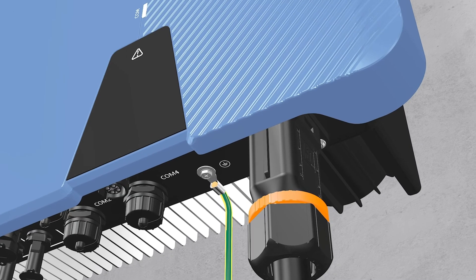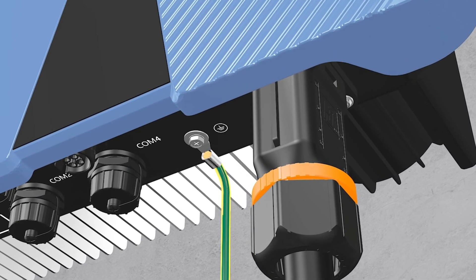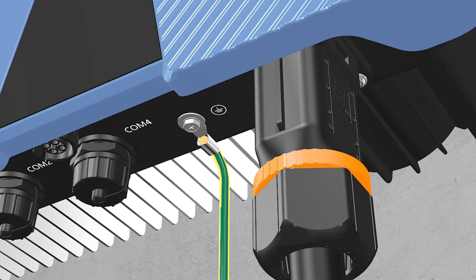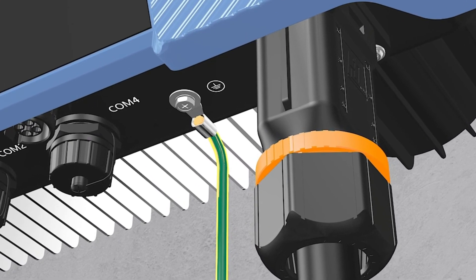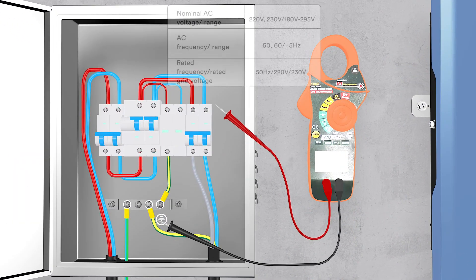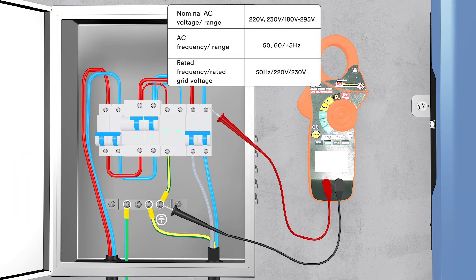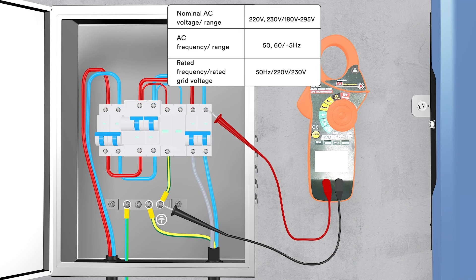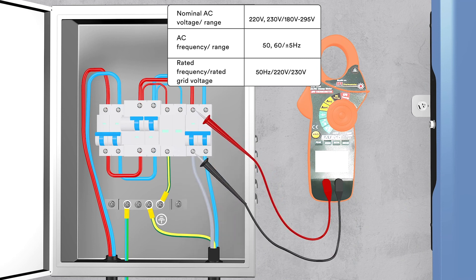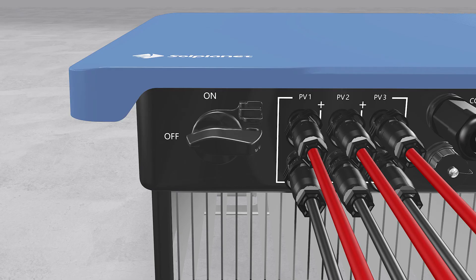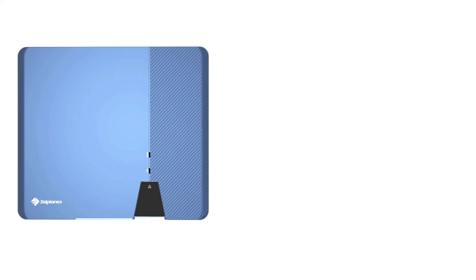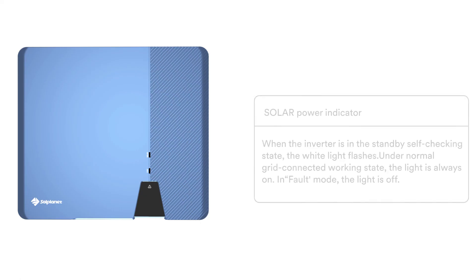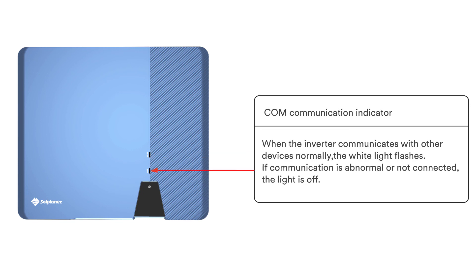Check the PE connection with a multimeter. Make sure that the inverter's exposed metal surface has a ground connection. Check the grid voltage. Check that the grid voltage at the point of connection of the inverter complies with the permitted value. Switch on the miniature circuit breaker and DC switch. The inverter is equipped with three LED indicators which provide information about the various operating states as follows.